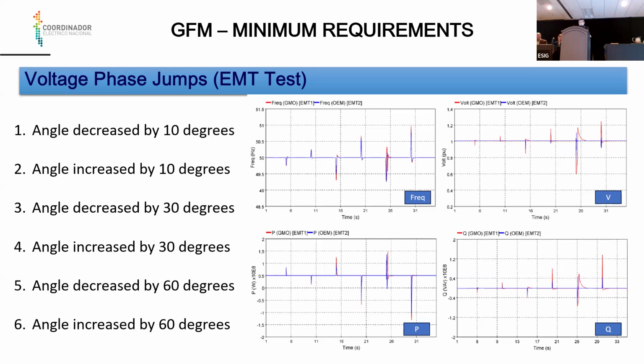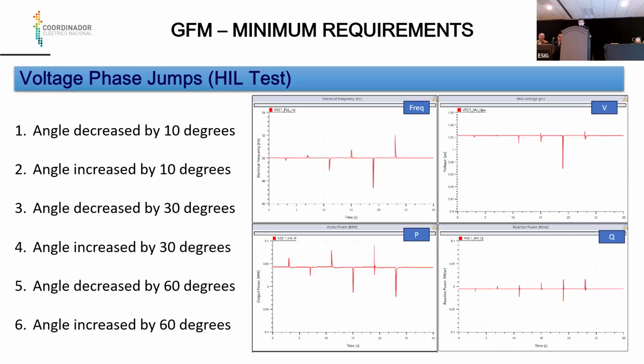Well, we can see that for each phase jump, the result was stable, the expected behavior of grid forming. And the same for the hardware-in-the-loop test with the real physical controller. In this case, the behavior was stable too, and according to what is expected in a grid forming technology.